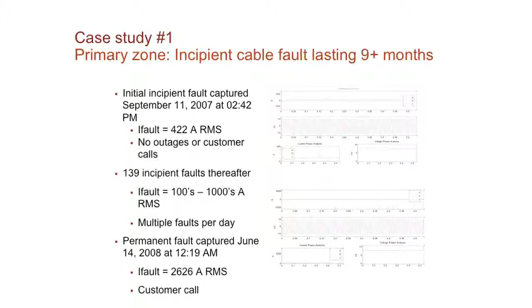Now, because we were kind of new and setting this up, the folks working the distribution system didn't know us - they could have done something like close the normally open switch and at least created a backfeed when this failed so they wouldn't have taken out all the customers. But we weren't at that stage where we were confident enough to say, hey, close that normally open switch because that's going to eventually fail. But it was very interesting. This is the kind of stuff that could be done with the reliability and the confidence buildup from the dispatchers when you're physically looking at that.